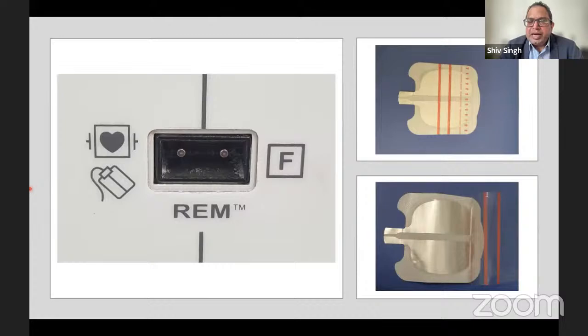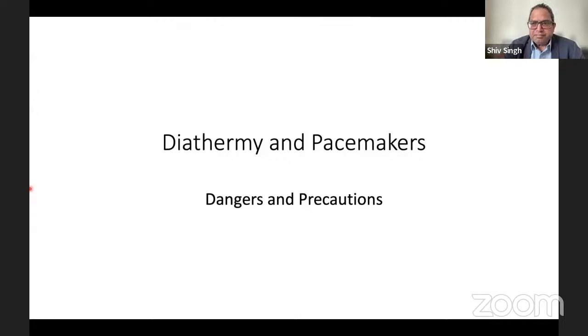This works only with pads which have two parts with a slit. This is a slit pad. You will see that this is not a single pad. It's got a slit and two conductive parts to it, and that's what makes it safer. If there is any disconnection or increased resistance or increased impedance, it will detect it. It detects the contact between the two plates, so unless there is a circuit completed between the two plates, it's not going to work.